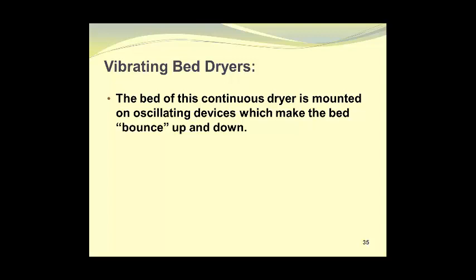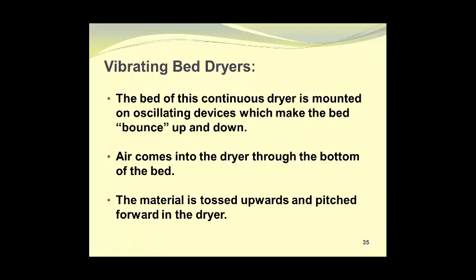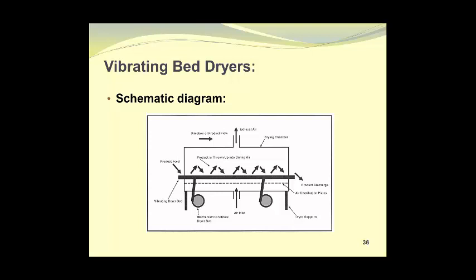For vibrating bed dryers, the bed of this continuous dryer is mounted on oscillating devices which make the bed bounce up and down. Air comes into the dryer through the bottom of the bed, and the material is tossed upwards and pitched forward in the dryer. Here is a rough schematic diagram showing the vibrating mechanism at the bottom. The product feed is at the left side, the product is thrown up into the drying air and moves along through the dryer, and is discharged at the right-hand side. Air distribution plates ensure uniform distribution of the heated air from the bottom of the dryer, and the exhaust air leaves through the stack at the top of the chamber.